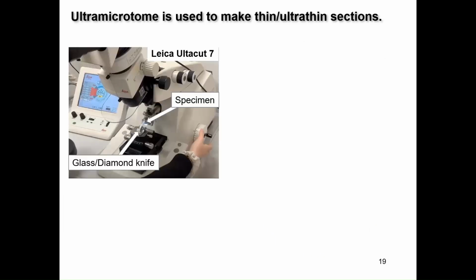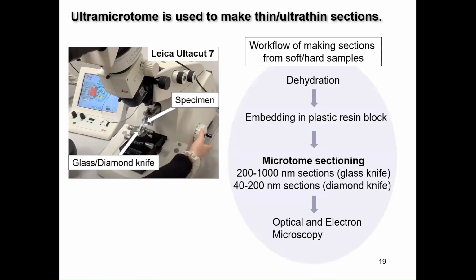Another sectioning tool is the ultramicrotome. We have the Leica UltraCut 7. Here is the specimen block, and here we have a glass knife in this photo. We can cut both soft and hard samples, and we use a glass knife or a diamond knife. If the samples are wet, we have to dehydrate them because we want to embed them in a plastic resin block, and plastic resin doesn't polymerise if there's water content.